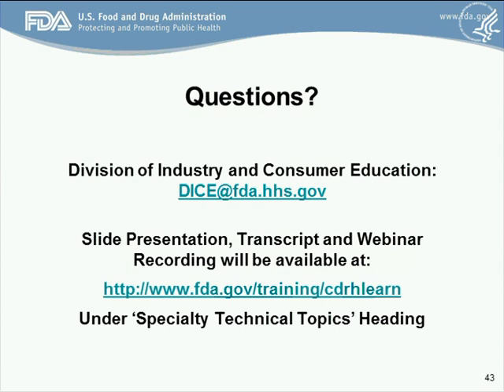The next question comes from Steven Ingles of Quality Solutions and Support. They support small business device manufacturers. On pyrogenicity testing required in 510K submissions, would it be acceptable if the manufacturer of the material provides the testing for the submission, versus testing the actual final device containing that material? The response: there are a lot of tests where we really want to see data based on the final finished product — this is an example of that. We don't know how materials or bio-burden or other contaminants might change from when the raw material is produced to what is on the final finished product.